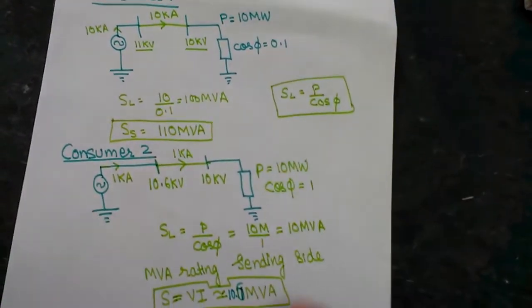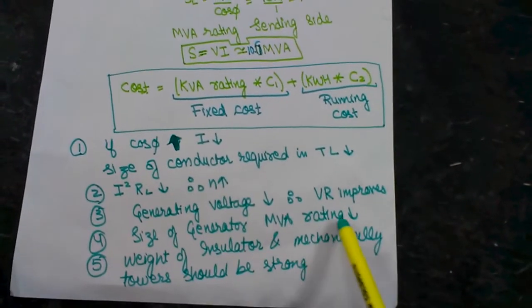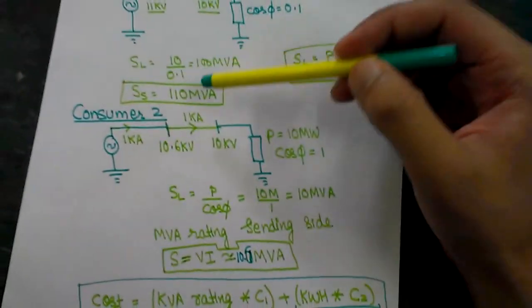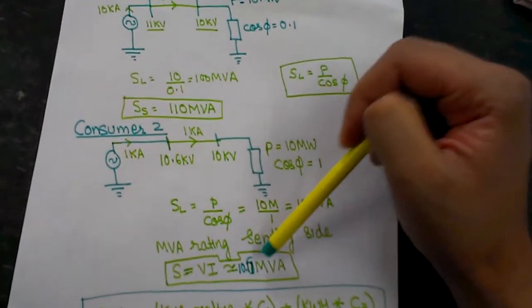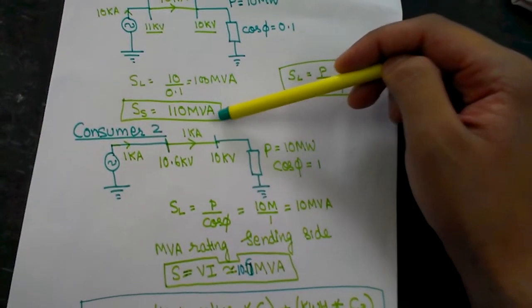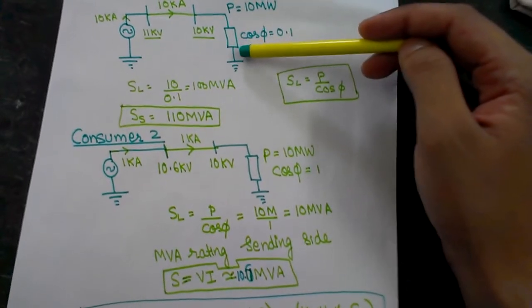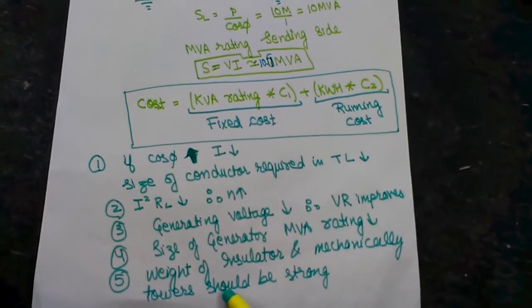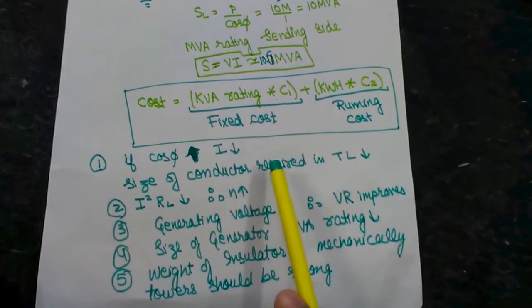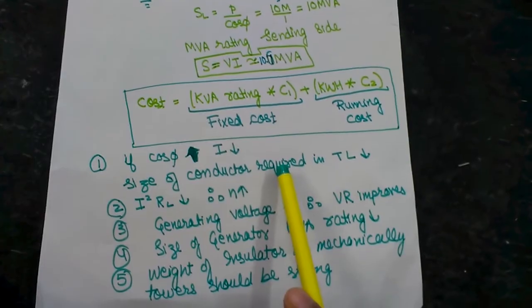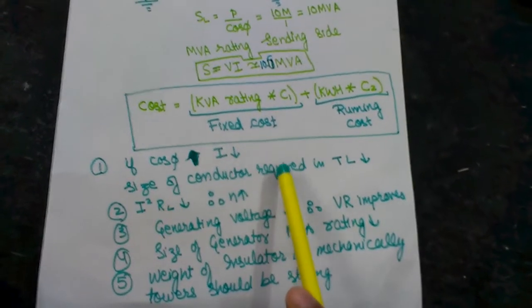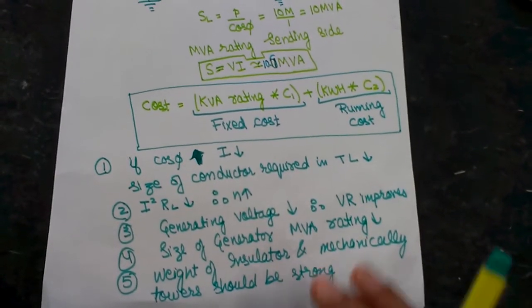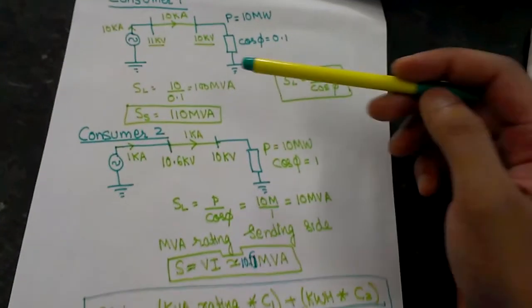The MVA rating — and therefore the physical size — of the generator also decreases. Here they had to generate 110 MVA versus only 10.6 MVA, so they need a bigger generator to supply the poor power factor customer. Finally, the weight of insulators and the mechanical strength of towers must be greater, because with a worse power factor the current is higher, the wires are thicker, and the insulators and towers must be strong enough to support the weight of those thick wires.